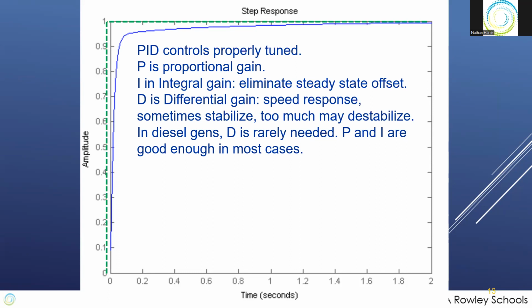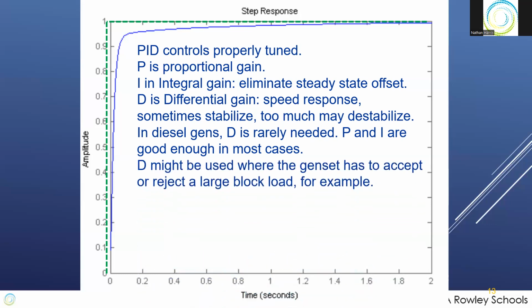We were doing marine applications, and we had one of the marine tests, I think for the outfit in England, I forgot the name of it, but they're a certification agency. And you actually had to drop a 70% load on a generator from 20% load to 90% load. And you had to recover in a certain period of time. And D really helped us to meet those needs in that case, adding some D into the system. So it might be used where it has to accept a large block load, for example, but it's not often used very much. But a little bit of D sometimes can help your system. So that's kind of a quick theory behind PID.